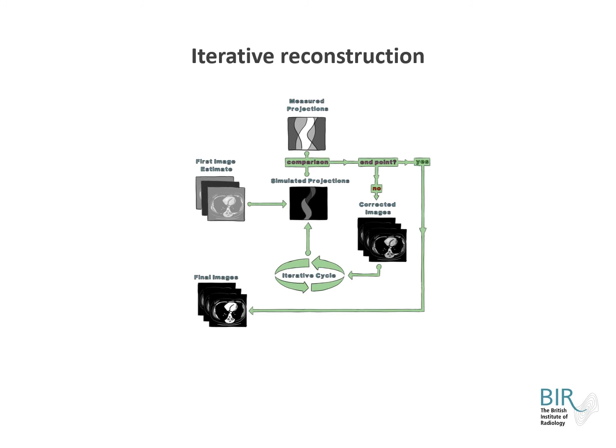Until relatively recently, CT scanners were reliant on a reconstruction algorithm called filtered back projection, or FBP. FBP is more susceptible to image noise than iterative reconstruction techniques that are commonly found on all modern scanners. FBP was favoured for many years as its relative simplicity resulted in near-live image reconstruction, whereas the complicated computation required for iterative reconstruction presented delays. Before we talk about iterative, you need to consider what was used prior to its availability. This was the process known as filtered back projection.